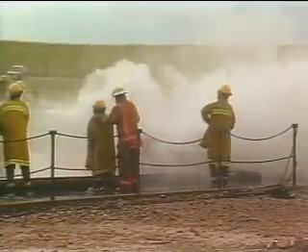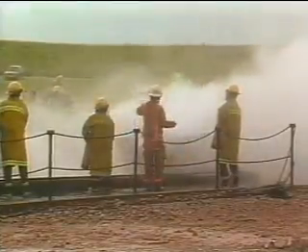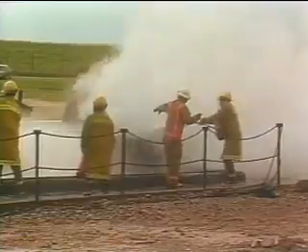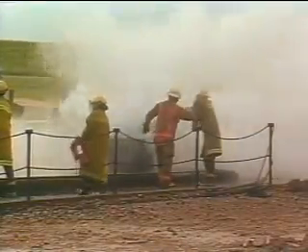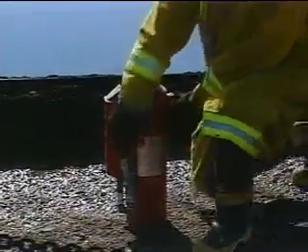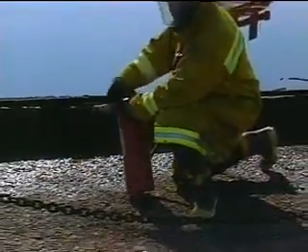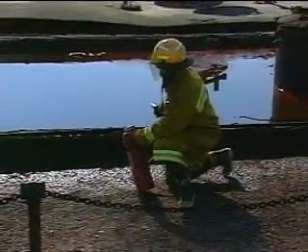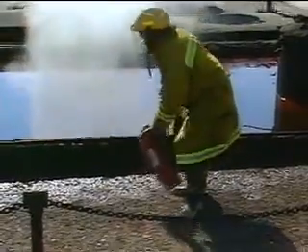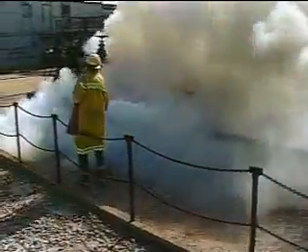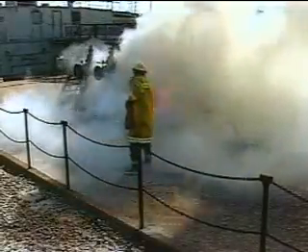Technique is so important because the average 20-pound dry chemical extinguisher is designed to deliver an effective stream for only 17 seconds. A 30-pound dry chemical extinguisher represents the weight of the agent inside. This extinguisher will only deliver an effective stream of agent for approximately 25 seconds. Larger extinguishers deliver a larger flow rate, so you have more extinguishing agent but not much more duration.